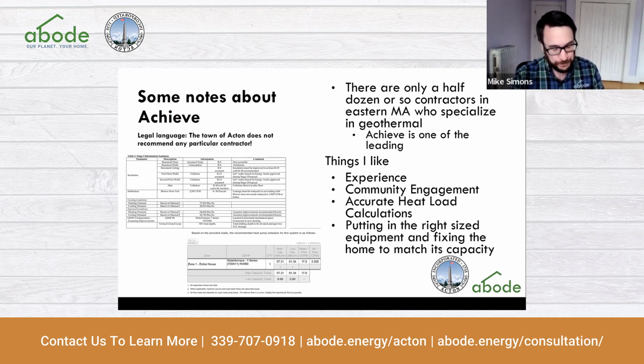Let me rephrase that. Every time I see an air source heat pump proposal, if the home's load is 70,000 BTUs, they're putting in 84,000 BTUs worth of equipment. There's hardly ever a discussion about doing the easy fixes to bring down the load. Some fixes may be more challenging to achieve, but what Larry really embodies, in a building science, BPI way, is the whole home approach. You shouldn't design a mechanical system around the inefficiencies of the building—you should fix some of the inefficiencies and design the mechanical system around that, because it will have lower operating costs, so all those savings are achieved.